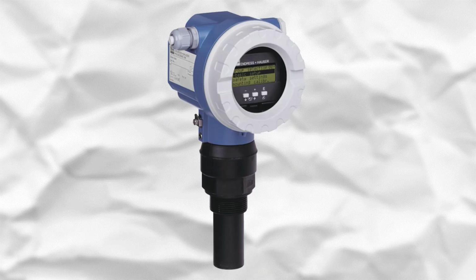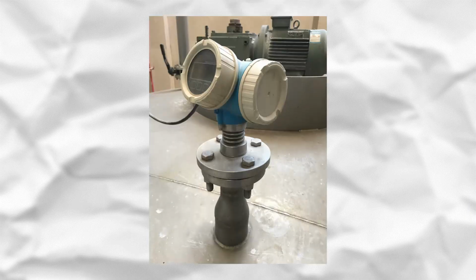As I mentioned before, ultrasonic waves are highly applied in level measurement. The ultrasonic level meters do not have high accuracy. Hence, they are used for simple and not valuable fluids. Installation of these sensors requires many considerations. For instance, the existence of foam on the surface of fluid, dust or vapor on top of the tank would have an awful effect on the accuracy and may make the sensor blind.